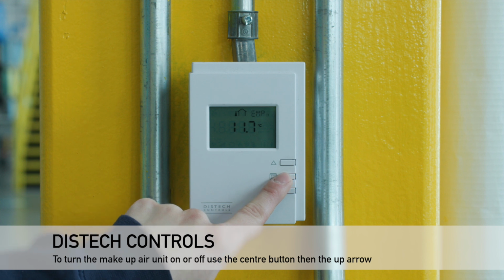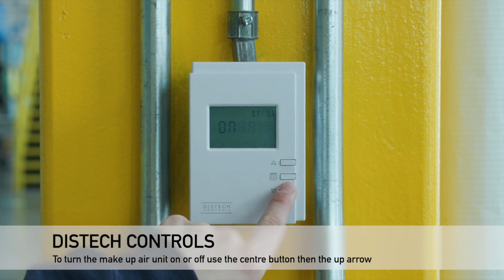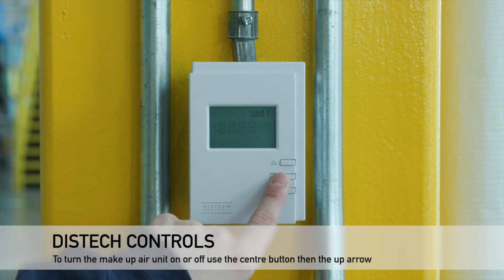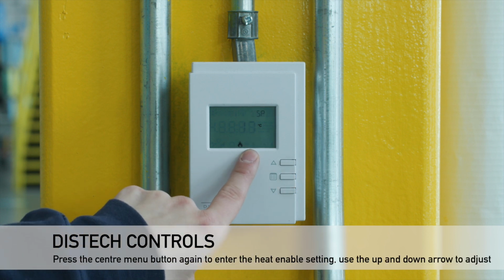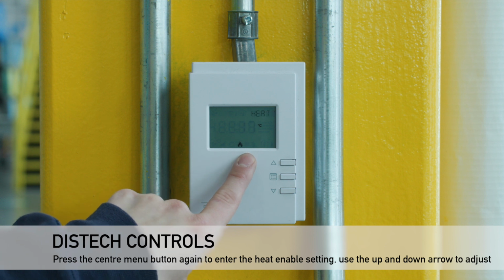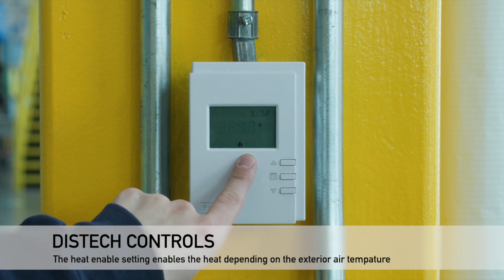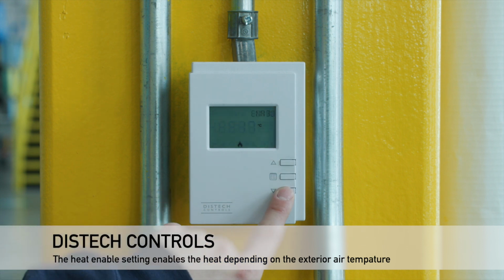To turn the makeup air unit on or off, click this button here, and click this button for on or off. This is the heat enable setting, which means that above 17 degrees, the heat will not come on. And if the temperature is below 17 degrees, then the heat will come on. So you can change it like this.